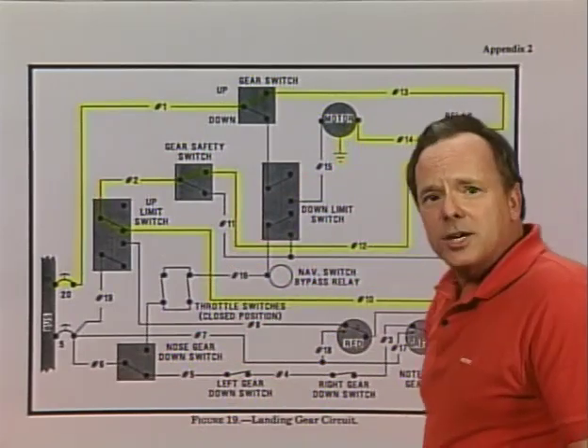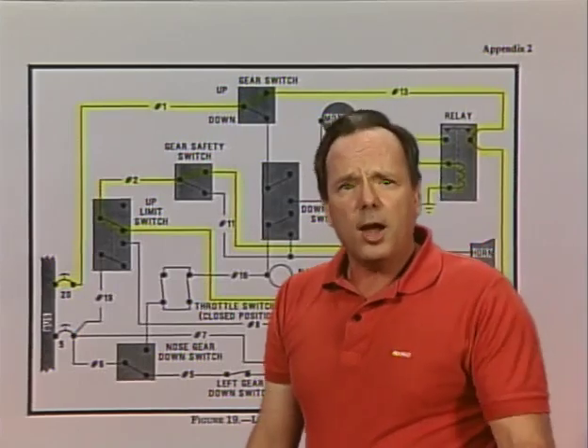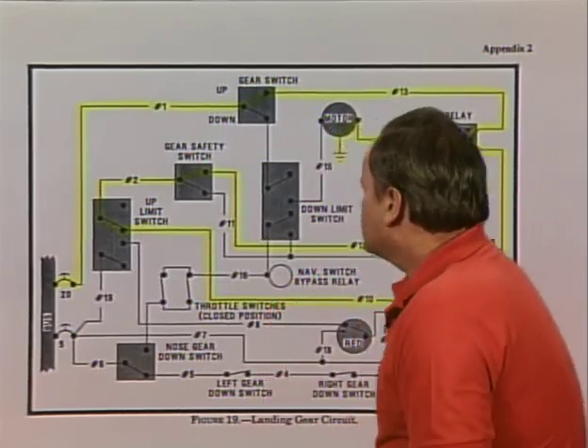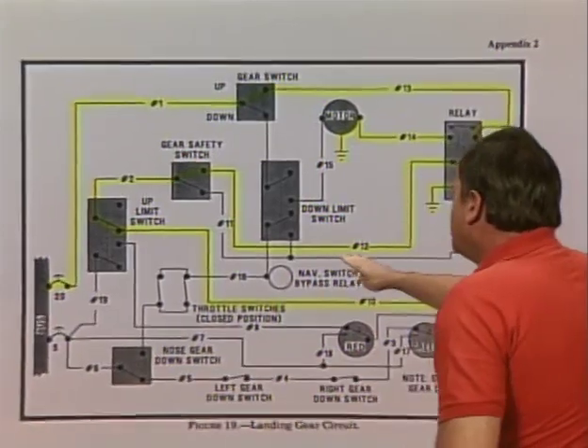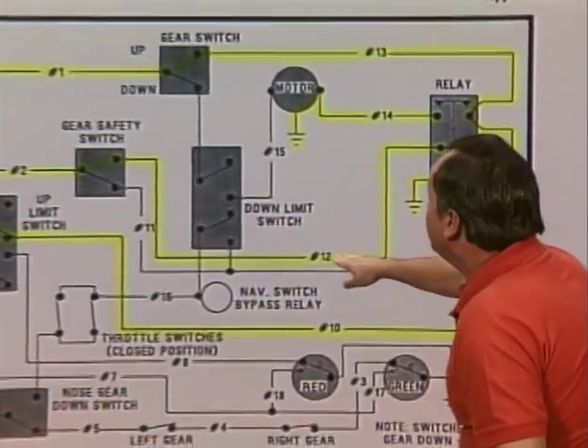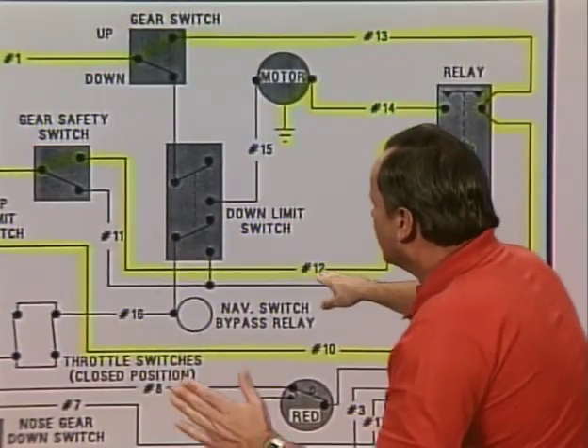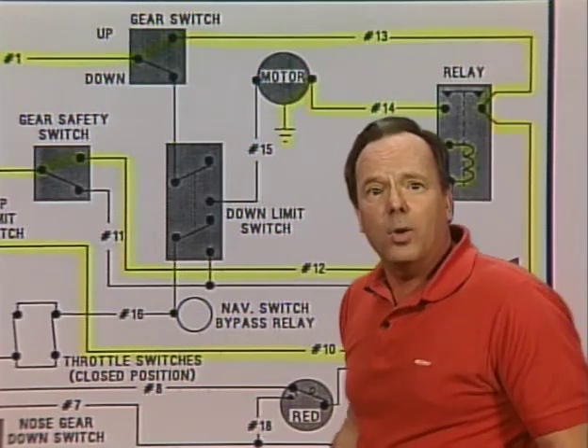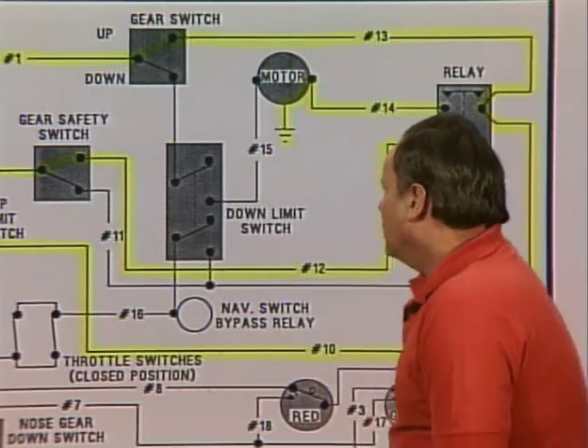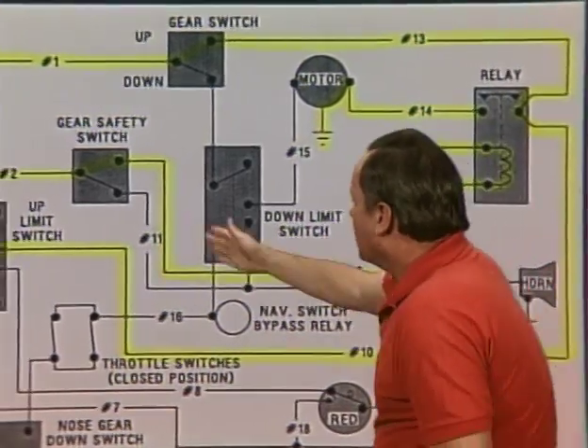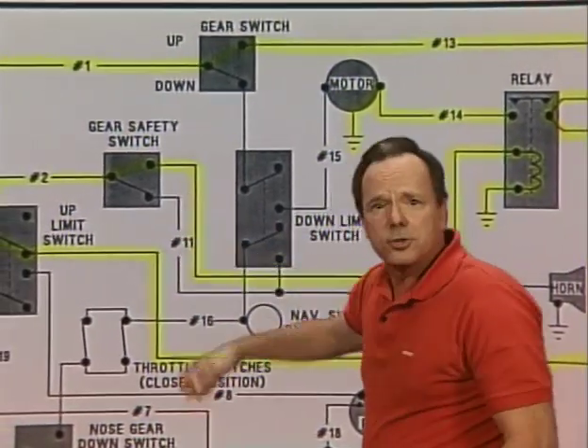So the FAA is going to ask you on the test, would you need to check wire 12? And the answer is, well, let's see where wire 12 is. Yes, we've put our circuit here in yellow. Wire 12 is in our circuit, so we would need to check wire 12. How about wire number 11? Would we need to check wire number 11? Well, no, wire number 11 is not in that circuit. It's over here, so that wouldn't be involved.